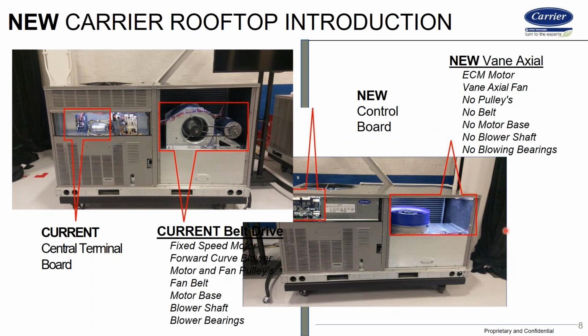So how do we tell if it's week 14? We look at our serial number. If that serial number is 1420, C whatever, right? That's our alphanumeric sequence. The first two numbers are our week of the year. The next two are the year. So a 1420 would be last week. A 1520 would be this week. Okay, so if it's a 1420 or newer, it should have the correction. And the easy way to do it is look at this switch right there. If you see a reset button in the middle of it, it hasn't been changed. If there's no reset button, then it is changed to auto, and you can follow these wires and it'll be in series with this limit switch.